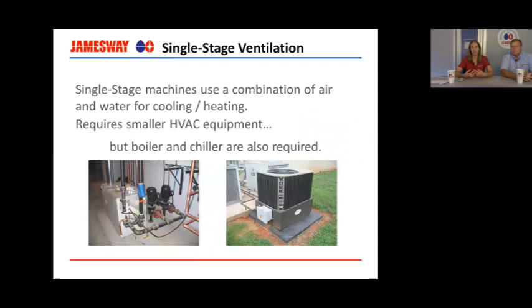So if we go to single-stage ventilation, our single-stage machines here at Jamesway use a combination of air and water for cooling and heating. So we would like to say that air is about 30% of the cooling in your cabinet, even though the air is actually there for oxygen. And then the chilled water in your system is providing about 70% of your cooling.